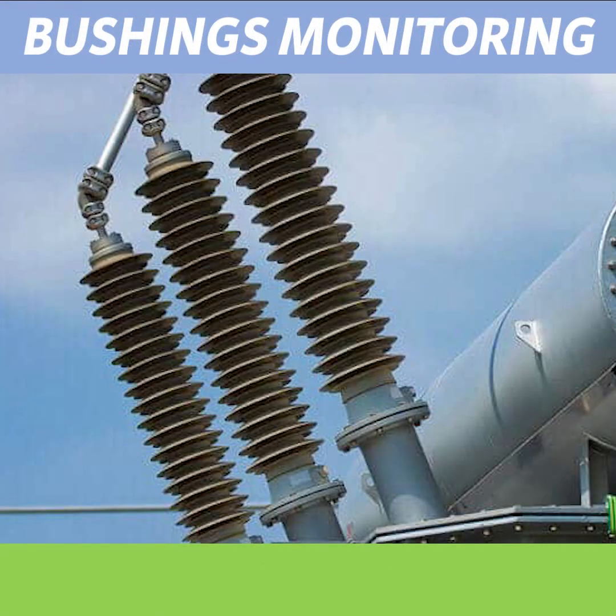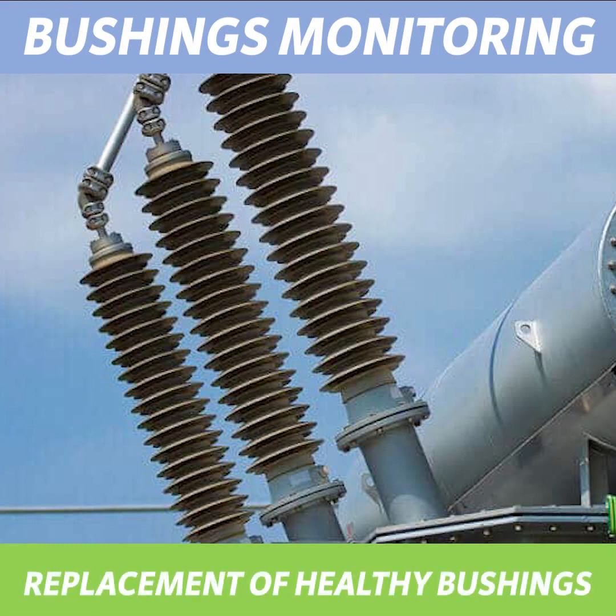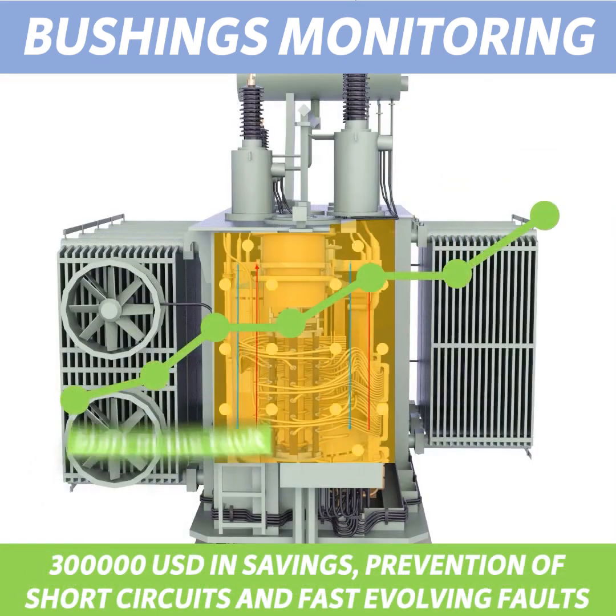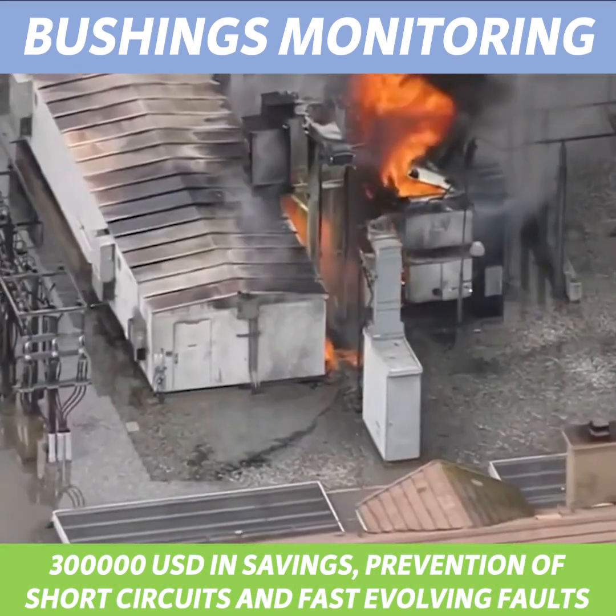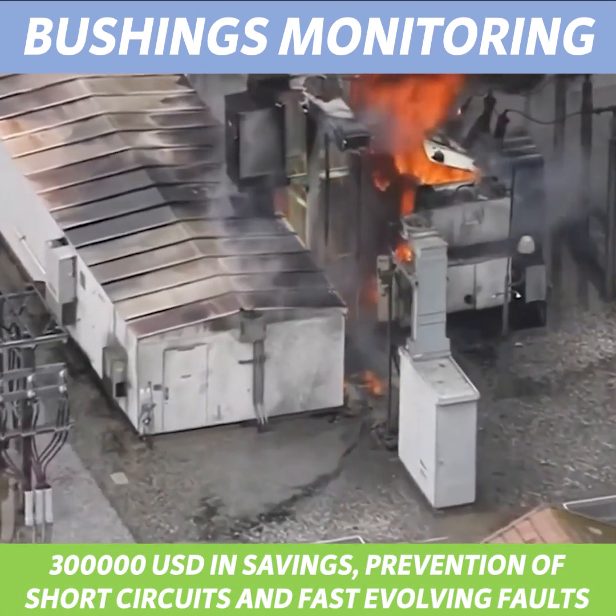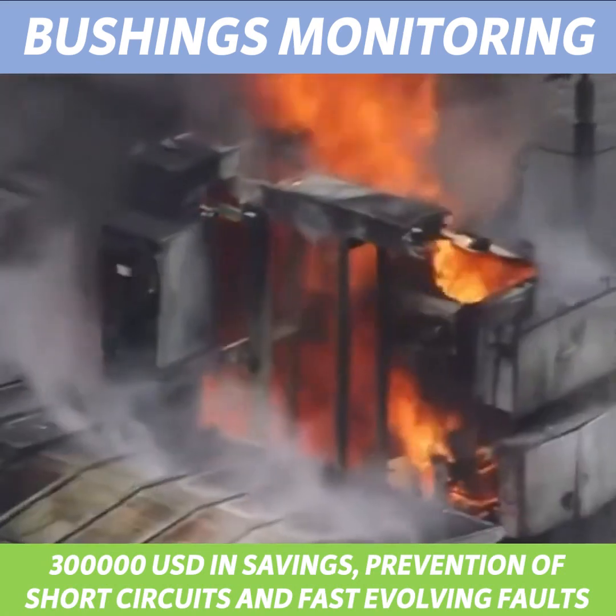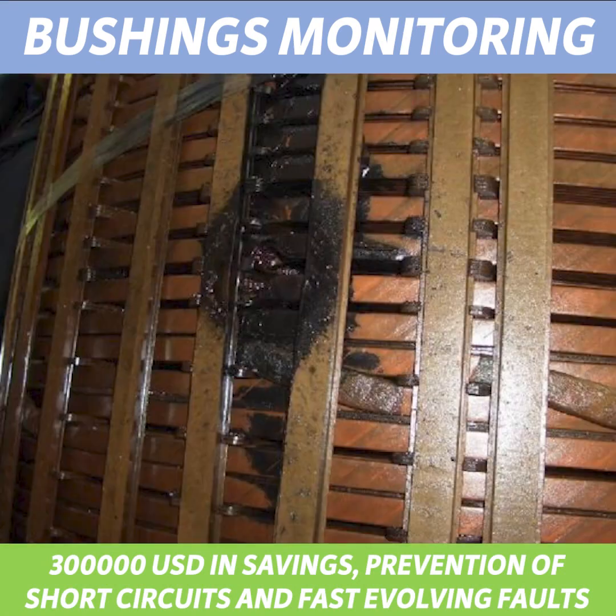Bushings monitoring is a very good investment as a contingency plan, as it may help identify a faulty bushing during service. This can help in planning bushing replacement while the old one is still in service, having a replacement bushing on site and cutting down replacement and ordering time. For fast evolving faults, bushing monitoring serves as a protection mechanism, preventing short circuit or transformer fire.